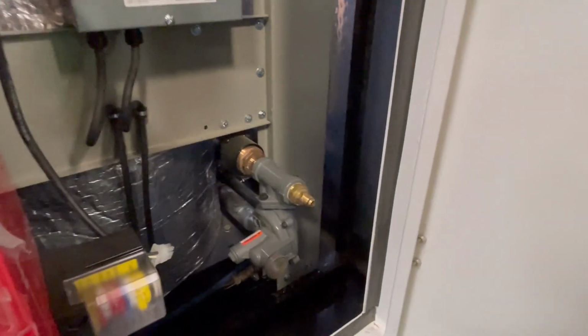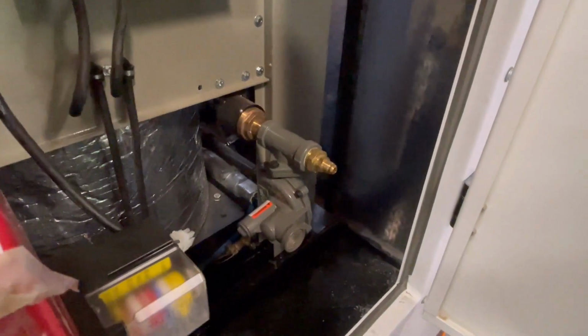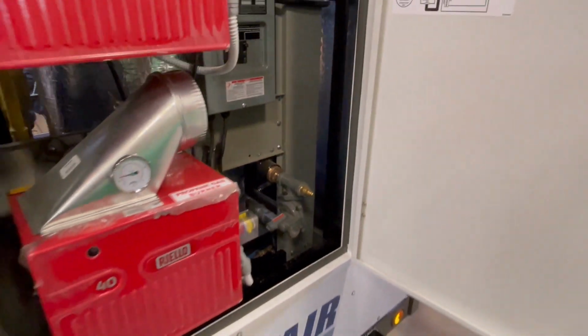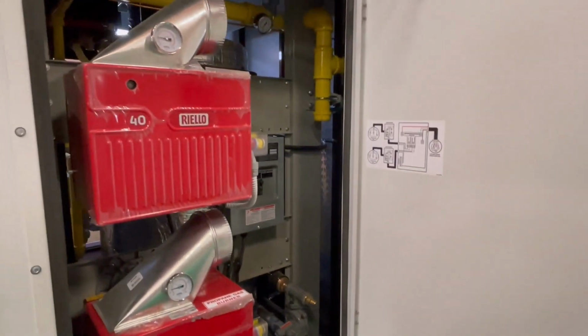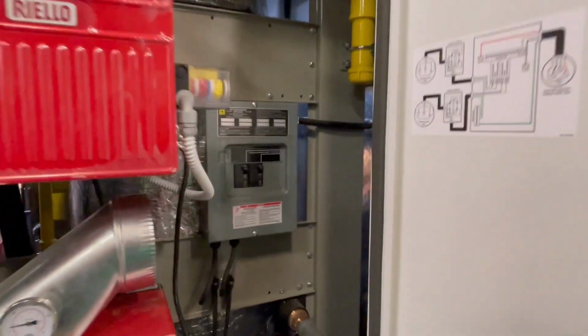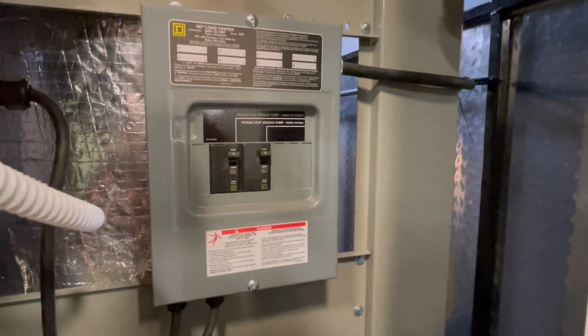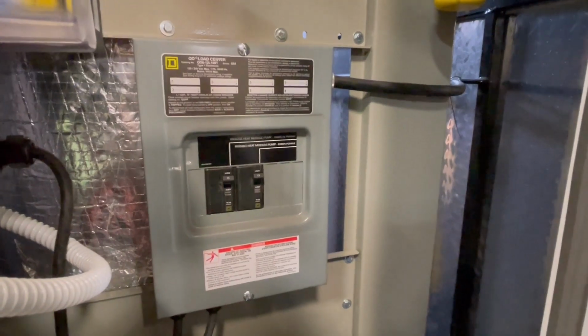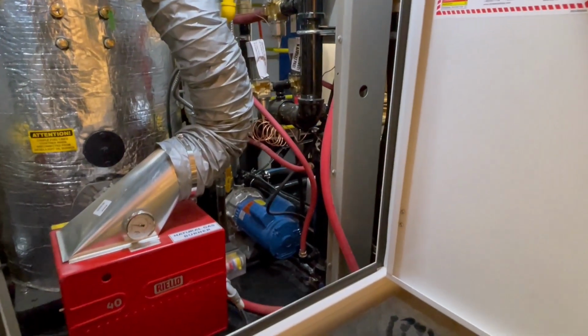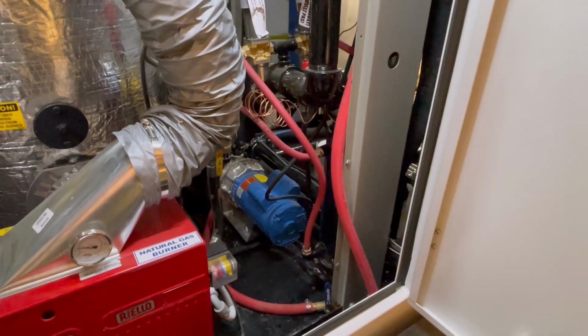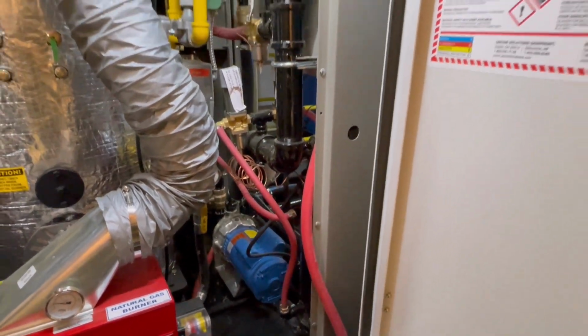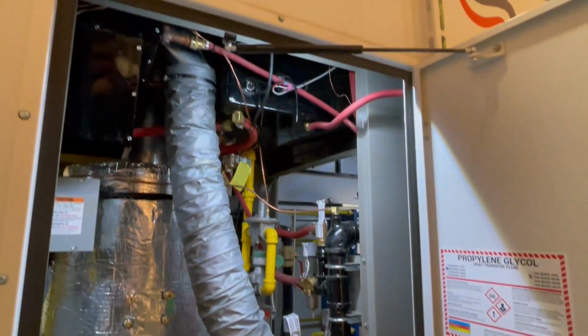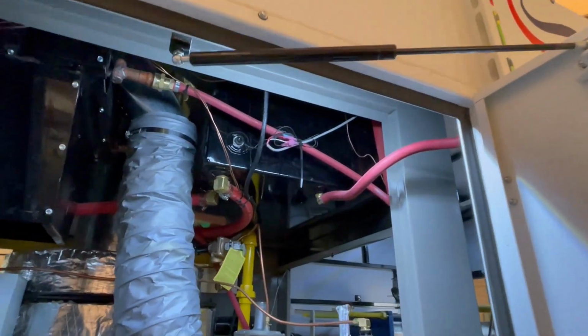There is a threaded storage on the side of the unit as well for a propane regulator that is supplied with the unit. This regulator can then be added to the inlet of the unit's gas train when propane is being used. Also above the regulator is the breaker box for the two pumps in the rear of the unit. A 3 horsepower pump delivers glycol through the system, and a glycol reservoir holds extra glycol and allows for glycol expansion in the system without creating pressure, as it is open to atmosphere.